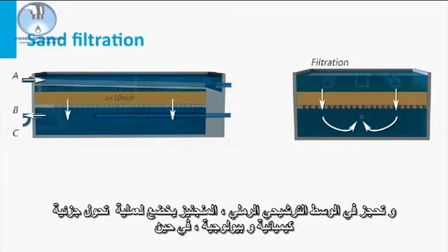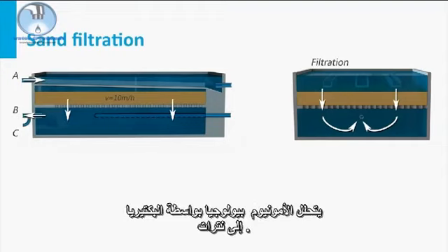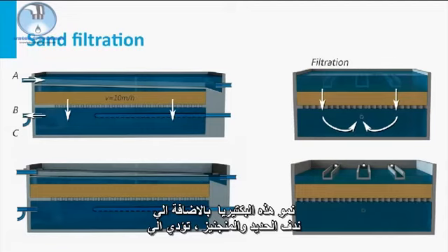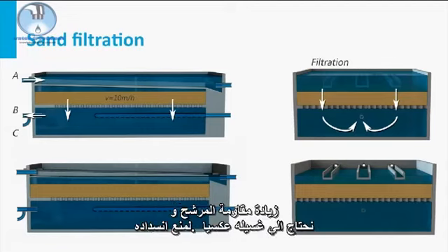filtration in the sand bed. Manganese undergoes a partial chemical and biological transformation, while ammonium is biologically degraded by bacteria to nitrate. The growth of these bacteria in combination with the iron and manganese flocs result in an increase of the filter resistance, and backwashing is needed to prevent clogging.